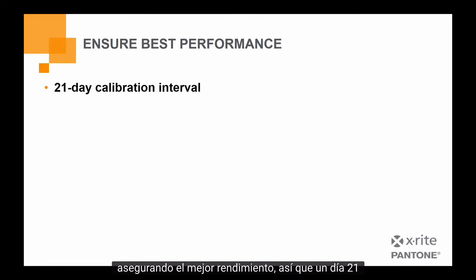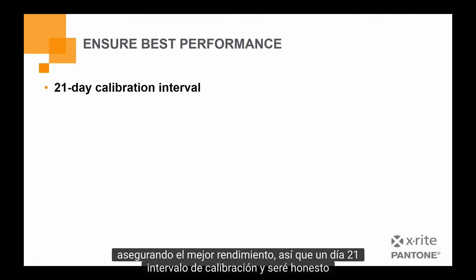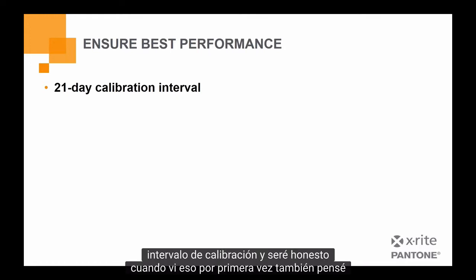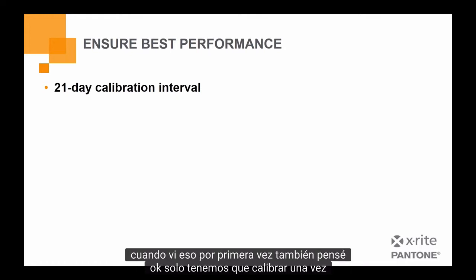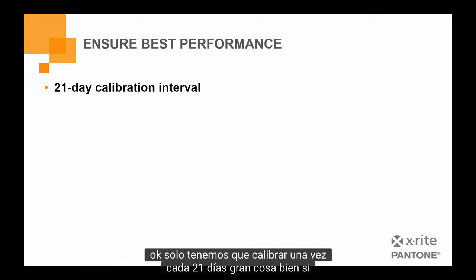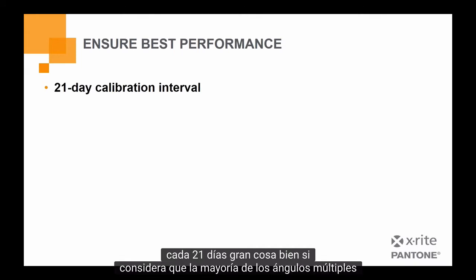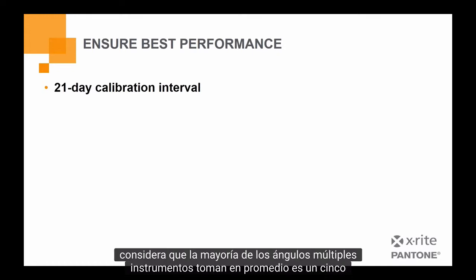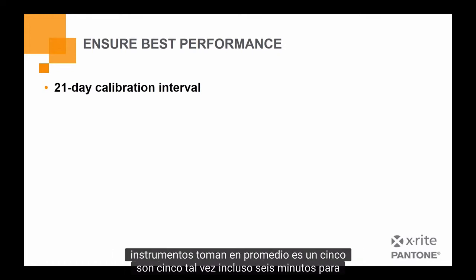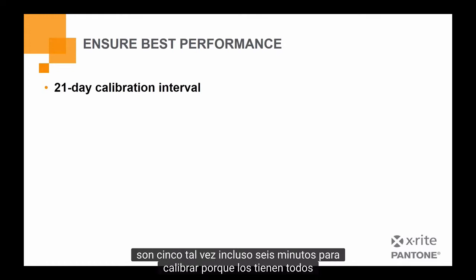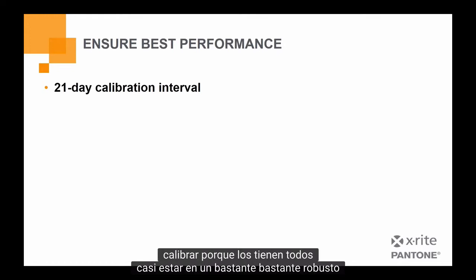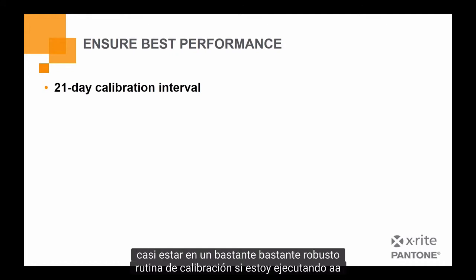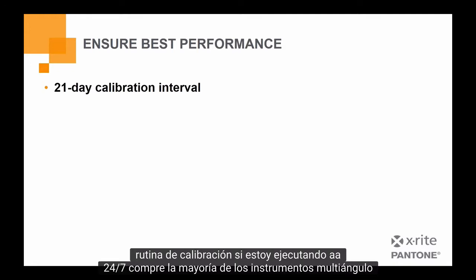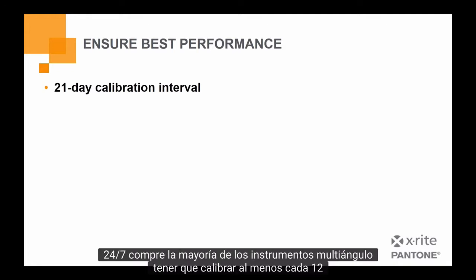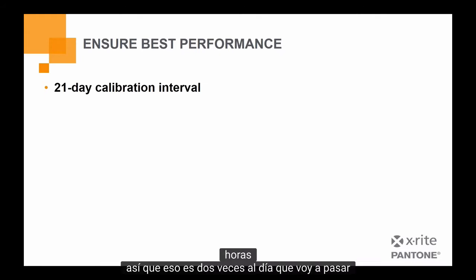So, ensuring best performance: a 21-day calibration interval. And I'll be honest, when I first saw that, I thought, okay, well, we only have to calibrate once every 21 days. Big deal. Well, if you consider that most multi-angle instruments take, on average, 5, maybe even 6 minutes to calibrate, because all multi-angle instruments have a fairly robust calibration routine. If I'm running a 24/7 shop, most multi-angle instruments have to calibrate at least every 12 hours. So that's twice a day.